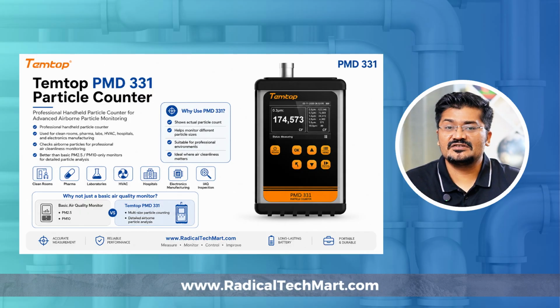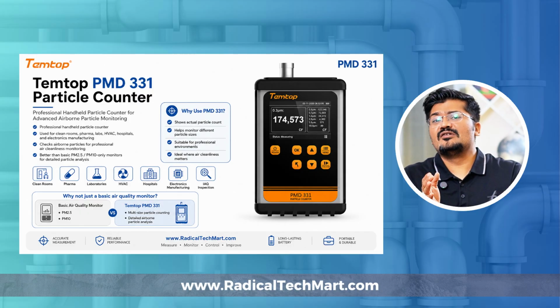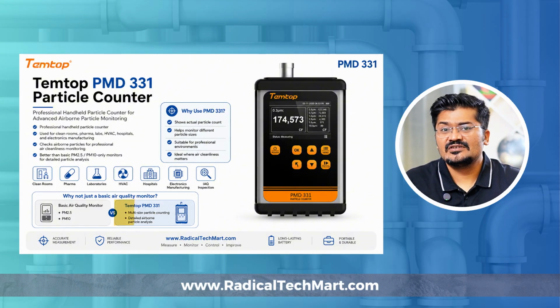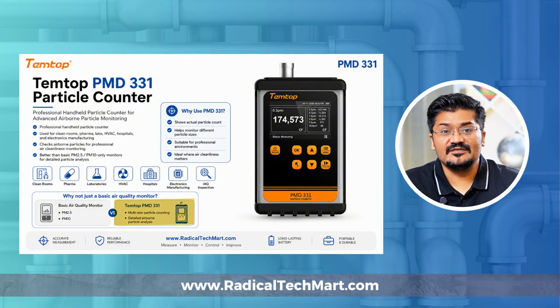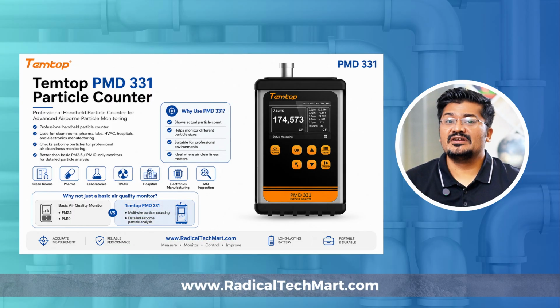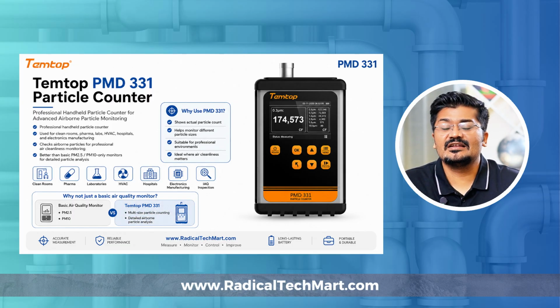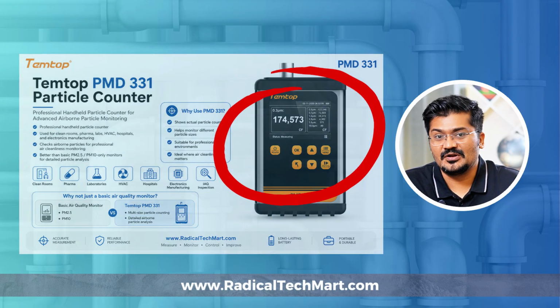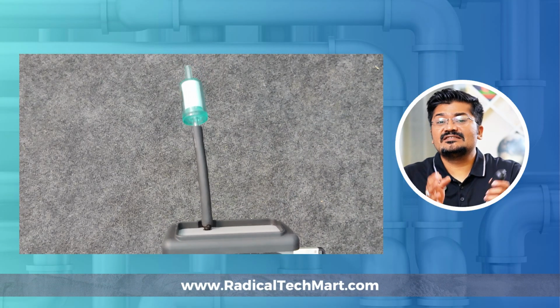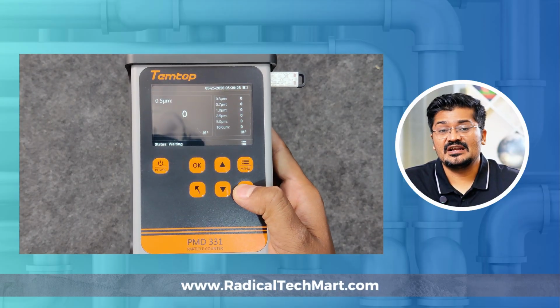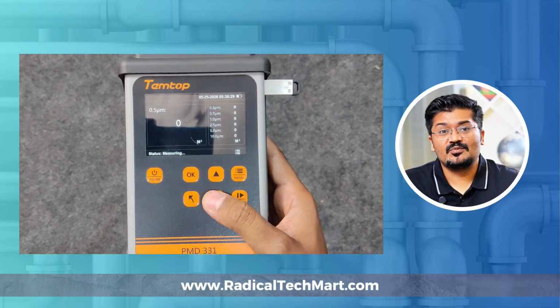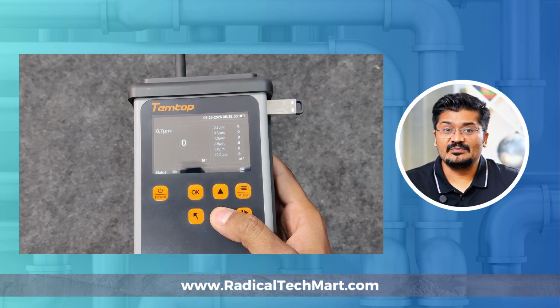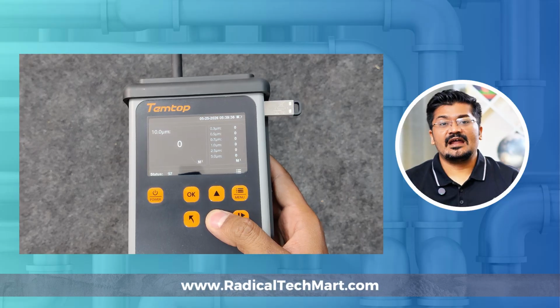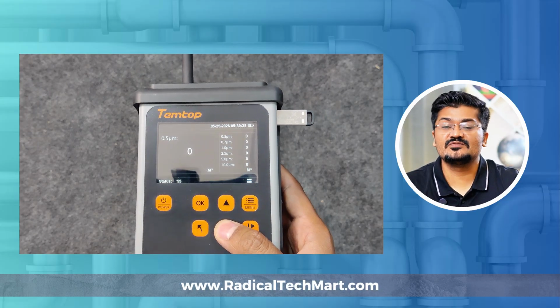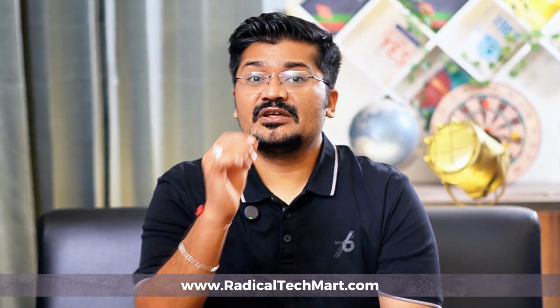But in these professional applications, only PM 2.5 value is not enough. Sometimes we need to know the actual particle count in different particle sizes. And for that type of detailed particle monitoring, we use a particle counter like Temtop PMD 331. PMD 331 can measure particles in 7 different size channels. It can detect 0.3 micron, 0.5 micron, even 0.7 micron, also 1 micron and 2.5 and up to 10 micron particles. So it helps the users to understand how clean the air is in a particular area.